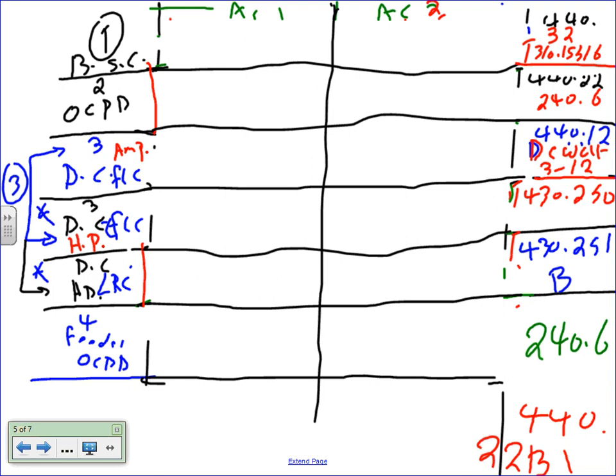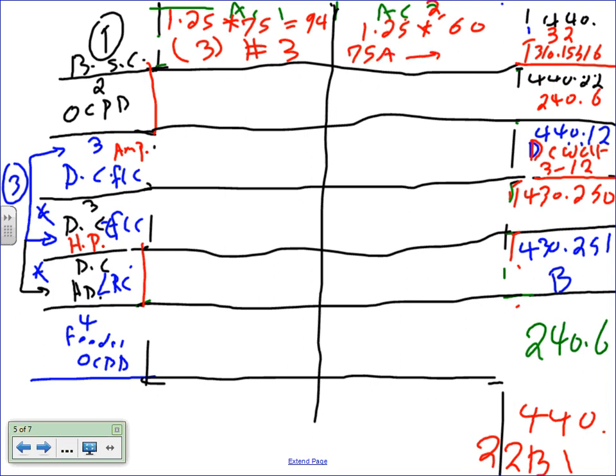Piece of cake. If you go there, it will tell you the conductor is 1.25 times the full load amps, which is 75, and that will get you a healthy 94. And if you go to the code, you're going to have 3 conductors, number 3, done. Second one, same thing, 1.25 multiplied by the full load amps of that baby, which was 60, yep, 60. And the math should be, if you go there, 75 amps, and then you go to the code, that will give you 3 conductors, number 4, done. 3 conductors, number 4. Any questions? Straightforward, 1.25, continuous current. Any question about this, guys? No gimmicks, nothing, like any other motor.